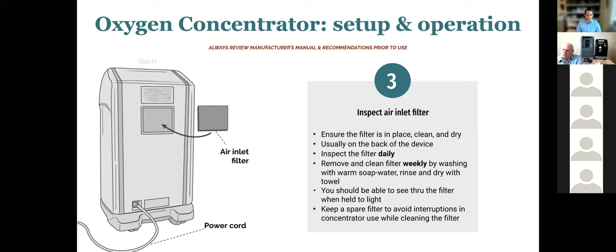Do not put these in a machine, and they must be completely dried before putting back in the machine. Ideally, have two of these. If you're going to be using the concentrator continuously, then while one is removed for cleaning, you can put in your spare, and as the first one is drying, you can be using the next one for the next few days. So keeping a spare air inlet filter is not a bad idea. When you do clean the air inlet filter, you should be able to hold it up to light and see light coming through it, just to give you a rough sense of function.